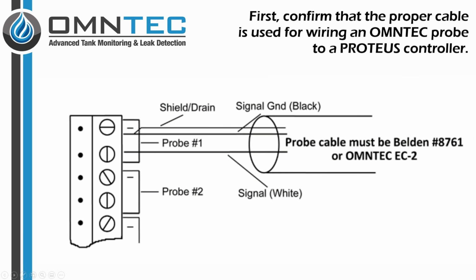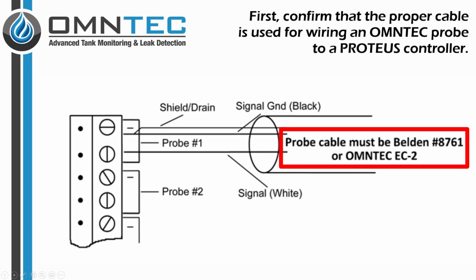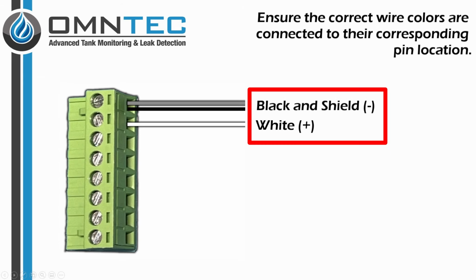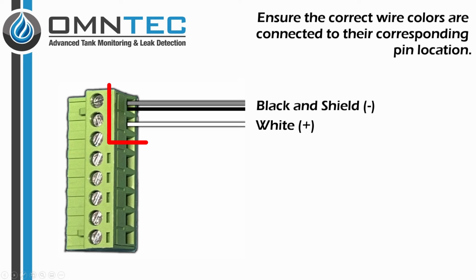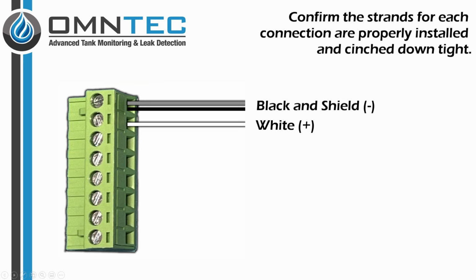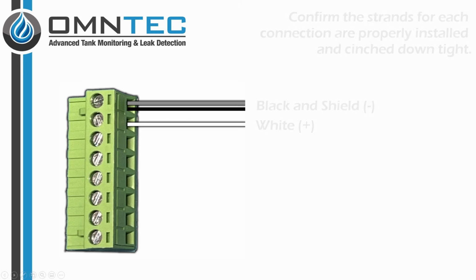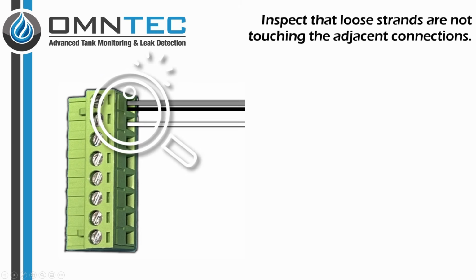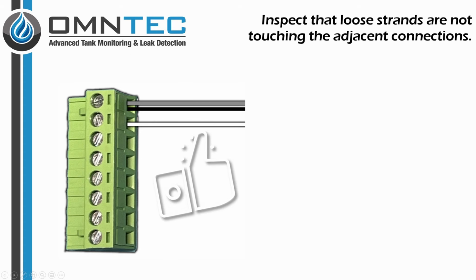First, confirm that the proper cable is used for wiring an OMNTEC probe to a Proteus controller. The proper cable is listed in the installation manual. Ensure the correct wire colors are connected to their corresponding pin location. Confirm the strands for each connection are properly installed and cinched down tight. Inspect that loose strands are not touching the adjacent connections.